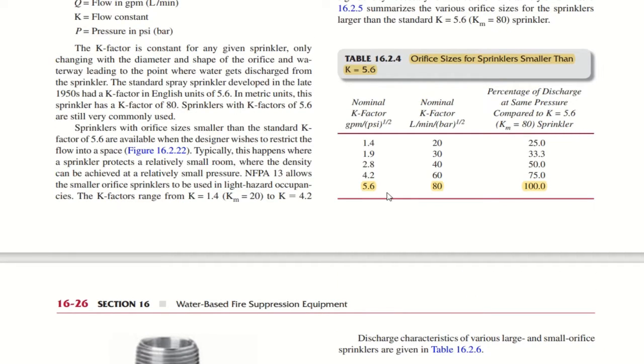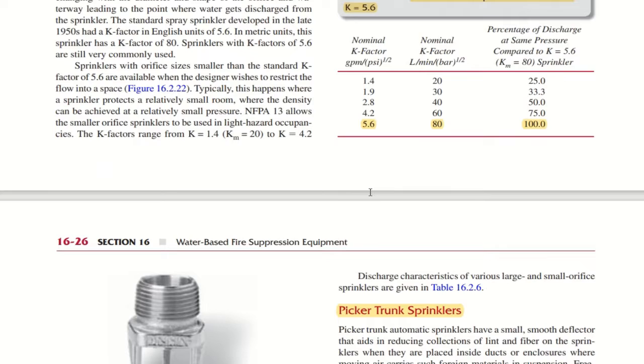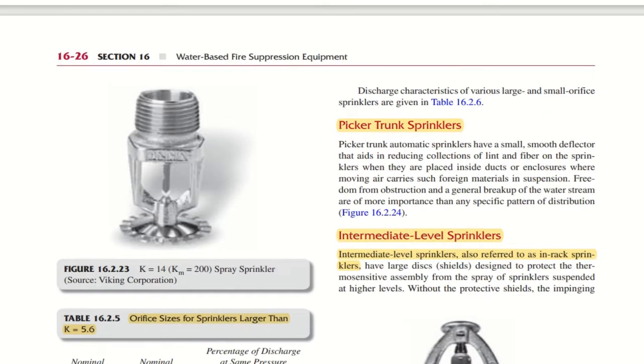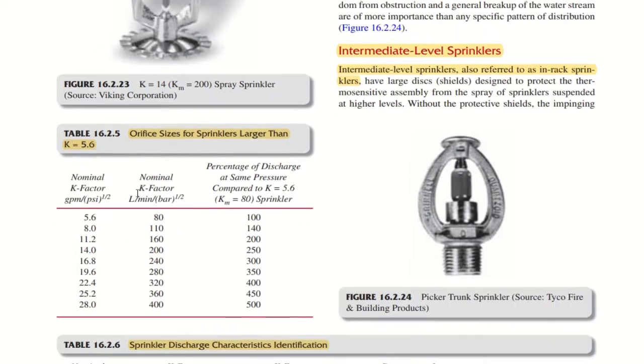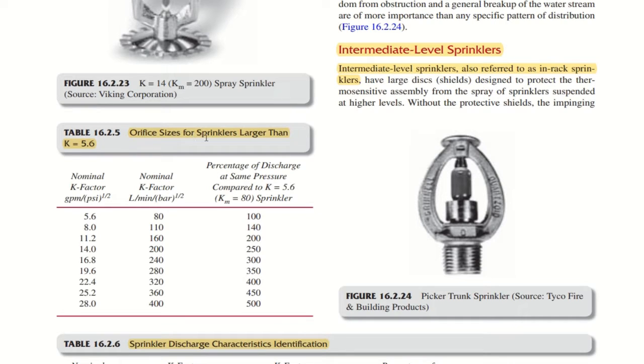Basically, if there are no specifications in the project, or if there is no specific data available, we will go with the K factor 5.6 for installation of any kind of sprinklers. However, if the area limitation is much higher, then we'll go with the higher K factors. Here there is one more table of K factor orifice sizes for sprinklers larger than K 5.6. If the K factor is higher than 5.6, then the discharge percentage at the same pressure compared to 5.6 will be this one. So you just have an idea about this.